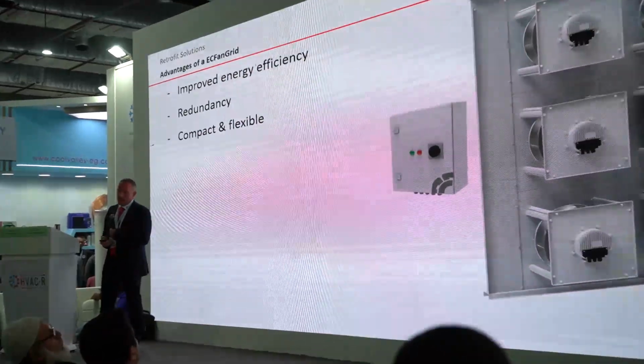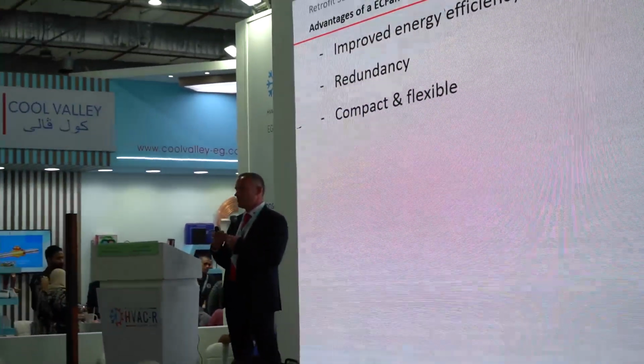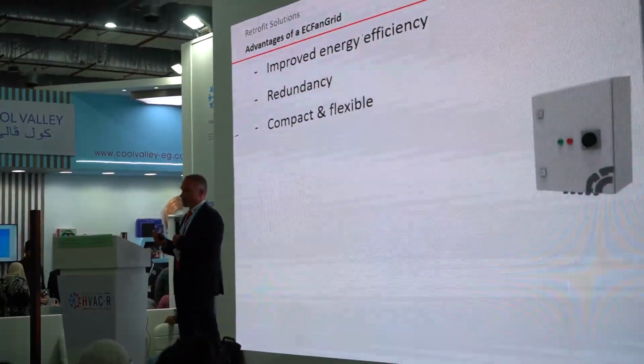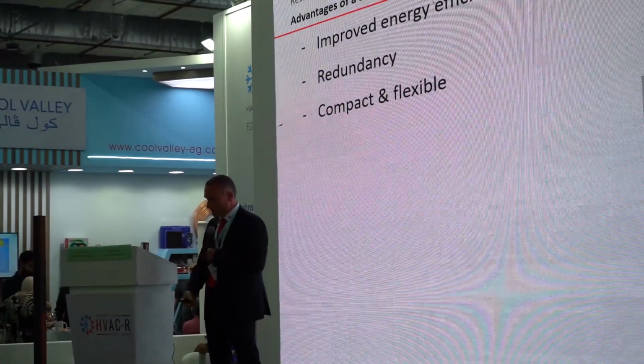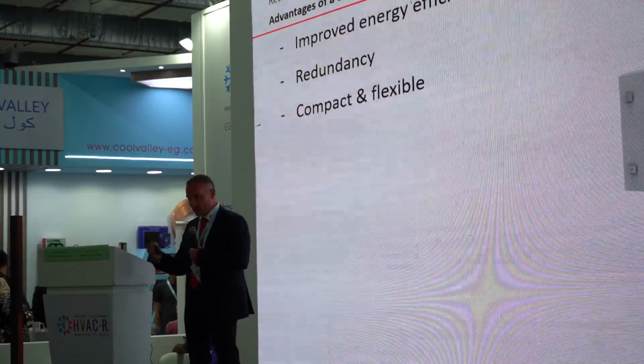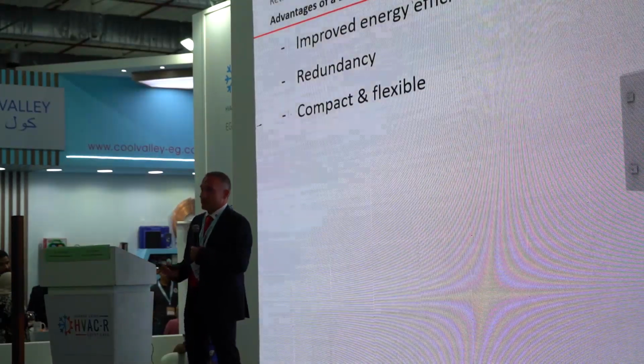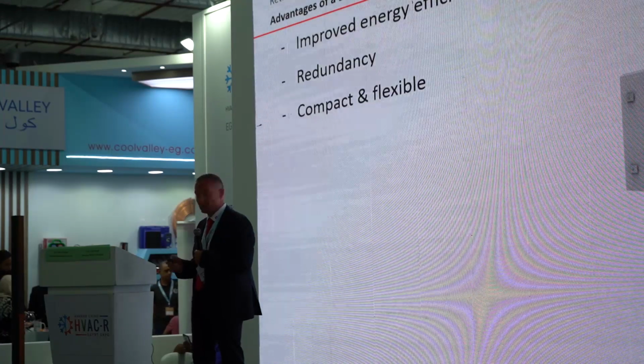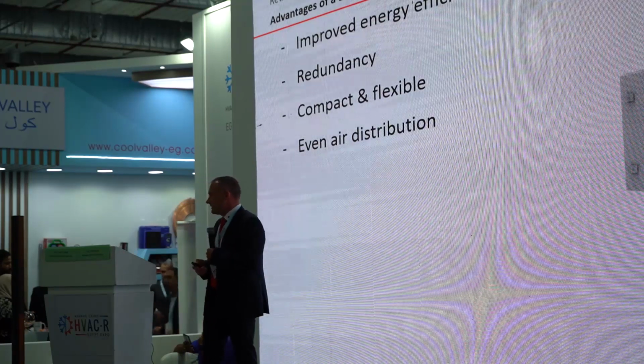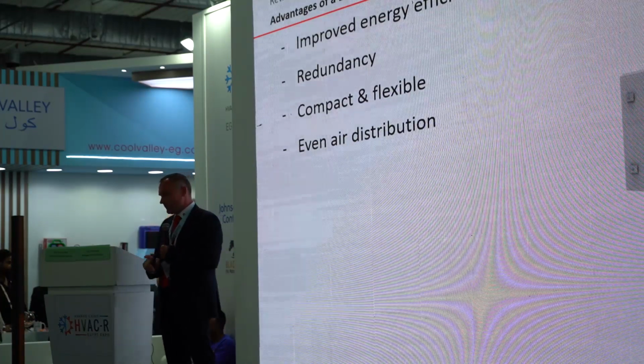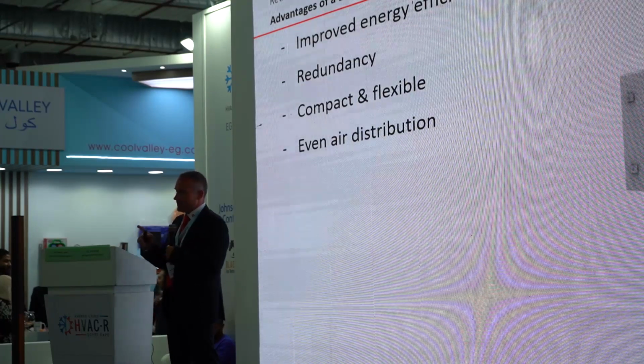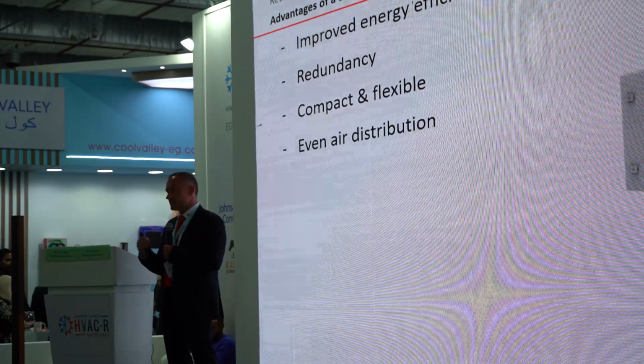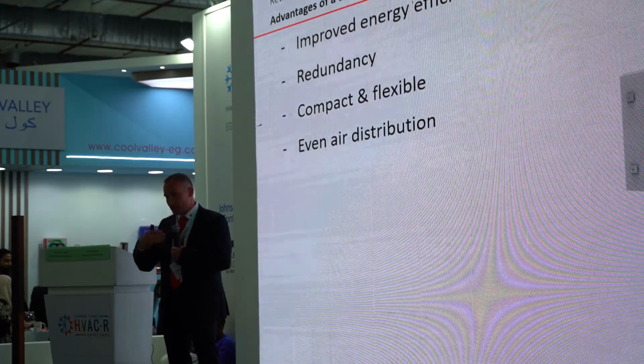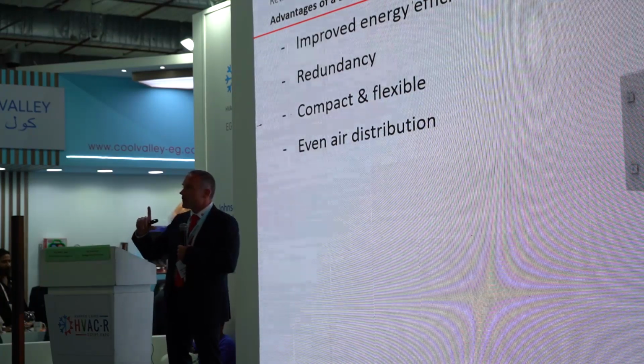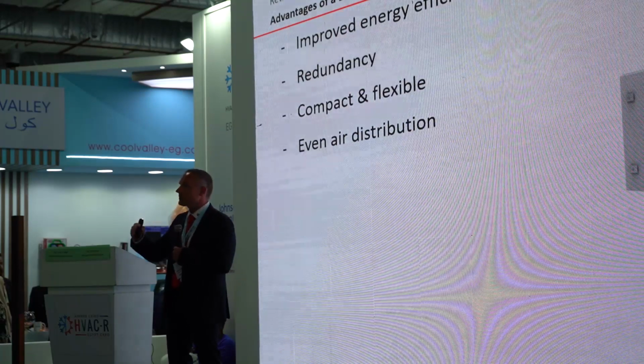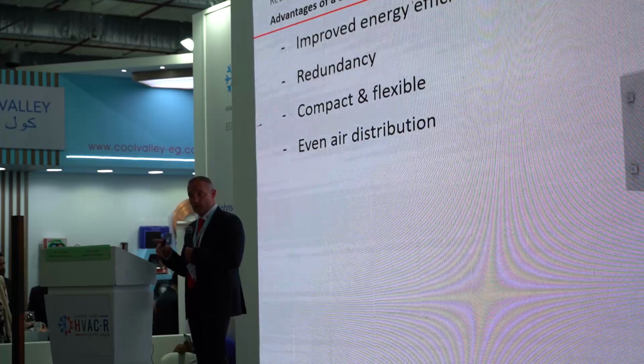Compact and flexible: one man is enough to install the EC fan grid. The maximum weight I'm talking about is 35, maybe 40 kg for the biggest fan. If you compare to a belt-driven big fan, the motor alone can weigh hundreds of kg. So when we design an EC fan grid, the fans are equally distributed in the channel, so the airflow is very constant and equal. You don't have just one hole where all the airflow and pressure is going through. We use the whole section of the AHU.